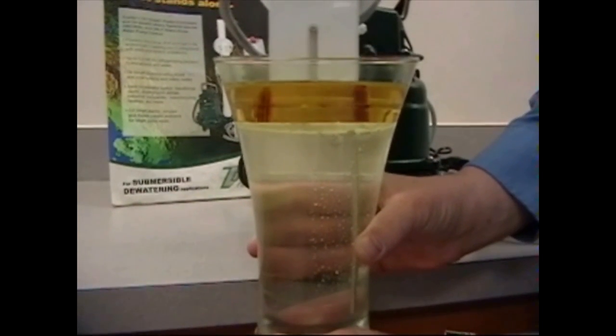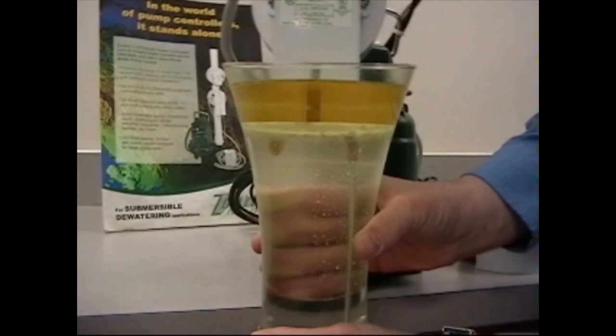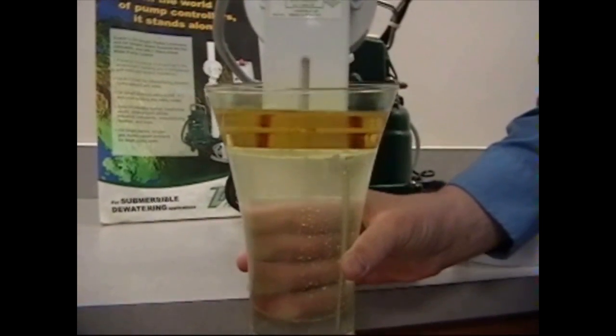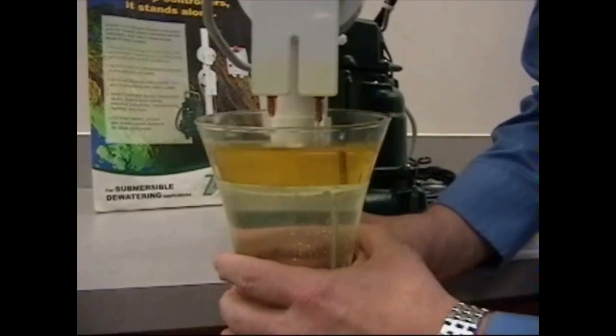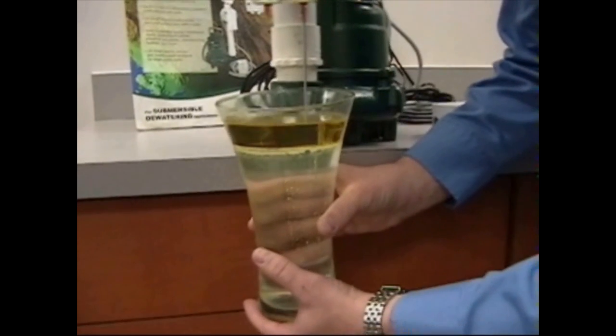Once it breaks the layer of oil and it comes in contact with water, the pump will turn on, and it will continue to run until the bottom probe is out of the water and only in the oil.